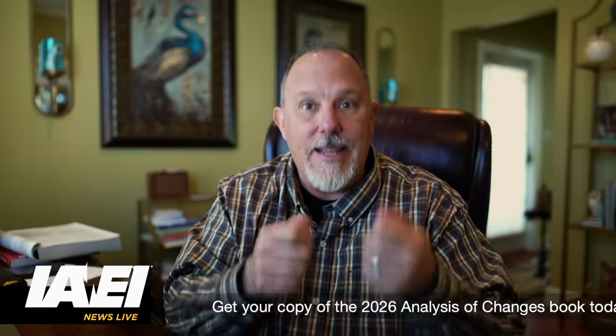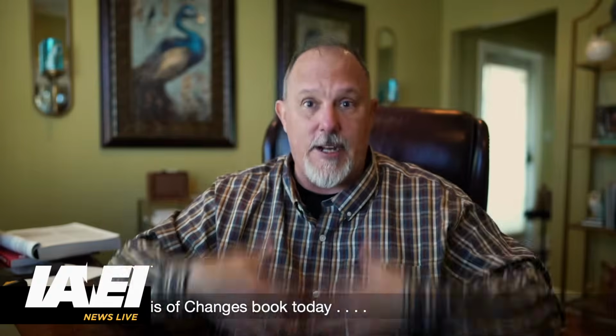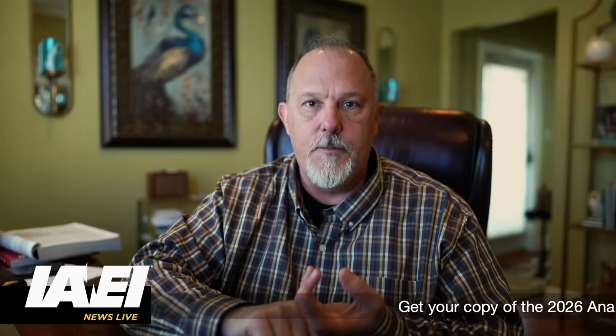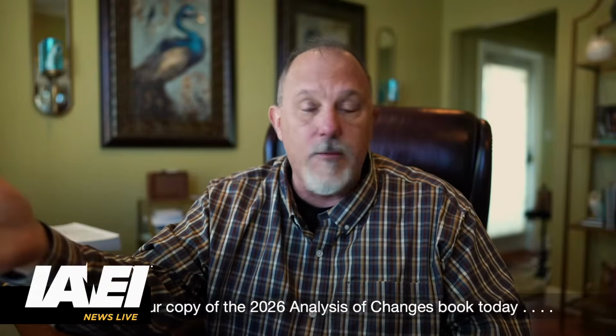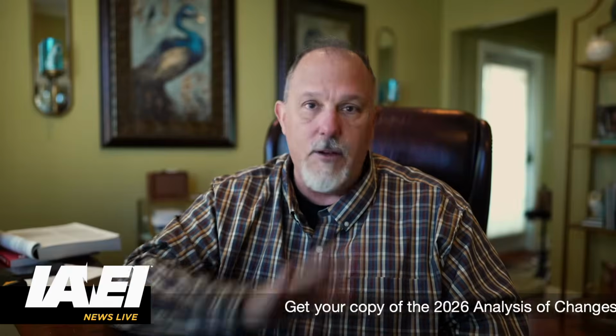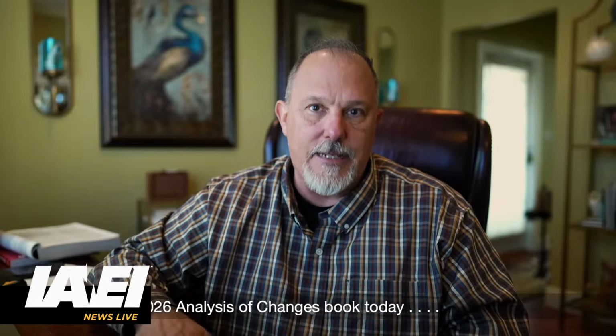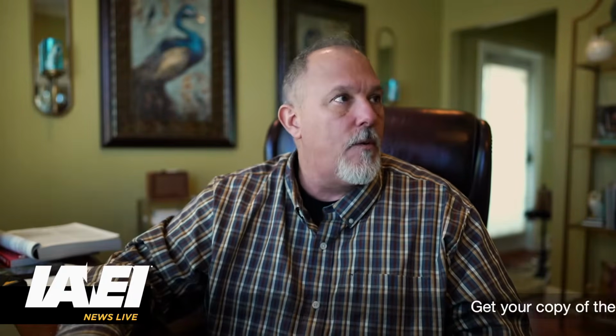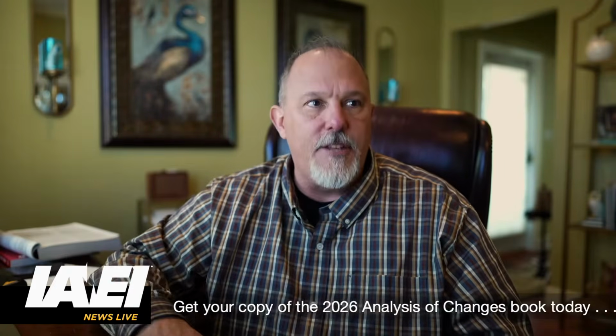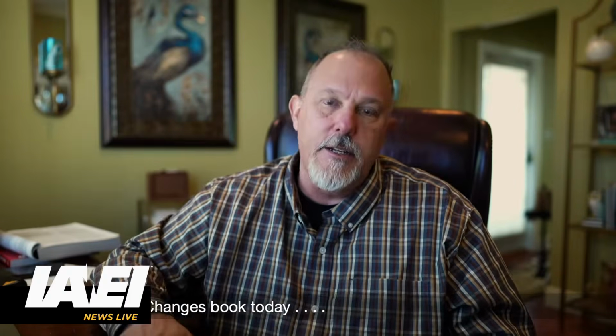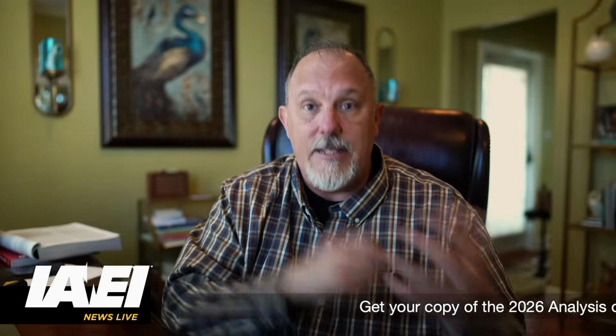That act is energized work because you have to assume it's energized. You've got to dress for the PPE. You've got to dress for the arc flash. You've got an arc flash risk assessment. You've got a shock risk assessment. You don't know if you turned off the right breaker or disconnected the right switch. You assume it is energized until you verify absence of voltage. So their argument is that, look, when you do this process, it's energized work. So then you go back to the code requirement, that is likely to require examination, adjustment, servicing, or maintenance while energized. Well, if you're going to maintain it, even if you're going to de-energize it, it's still energized until you verify absence of voltage.